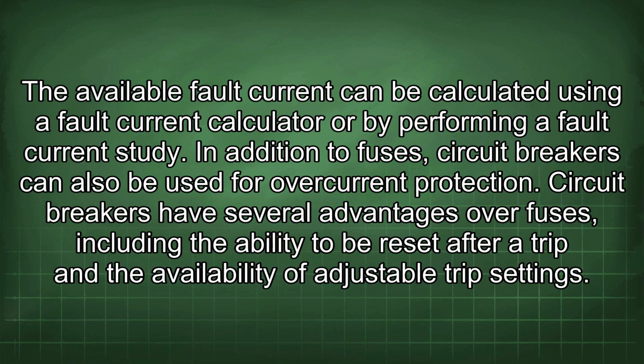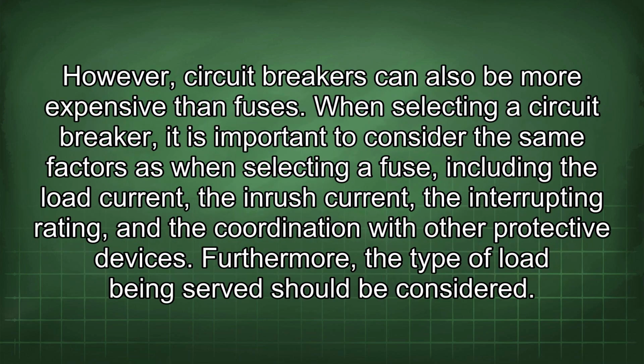In addition to fuses, circuit breakers can also be used for overcurrent protection. Circuit breakers have several advantages over fuses, including the ability to be reset after a trip and the availability of adjustable trip settings. However, circuit breakers can also be more expensive than fuses. When selecting a circuit breaker, it is important to consider the same factors as when selecting a fuse, including the load current, the inrush current, the interrupting rating, and the coordination with other protective devices.